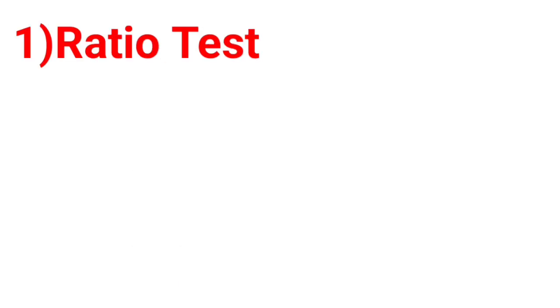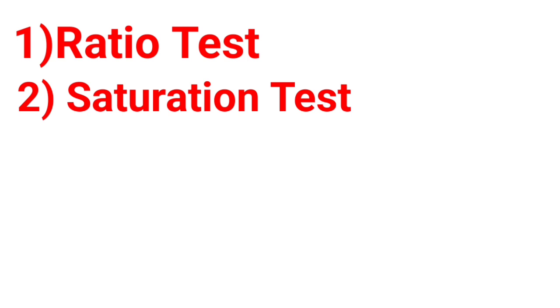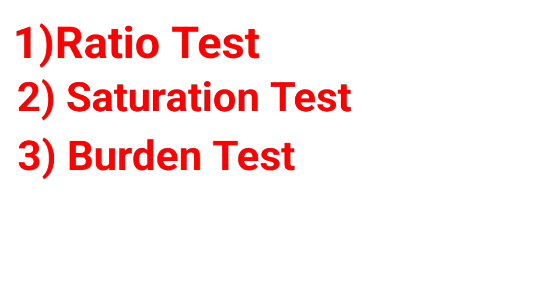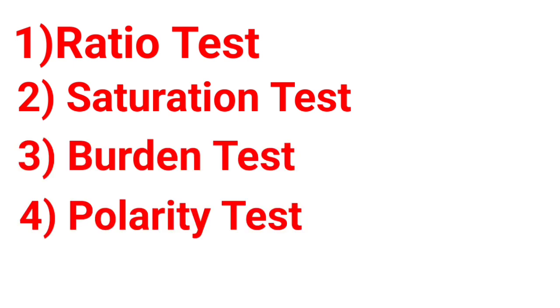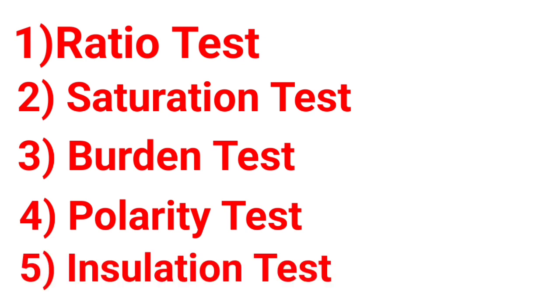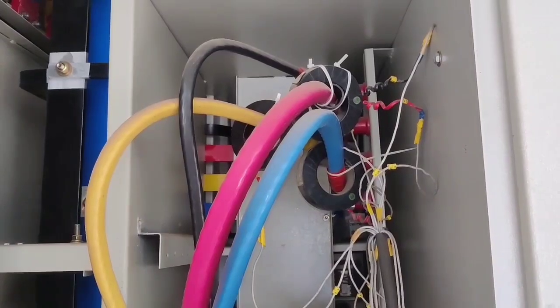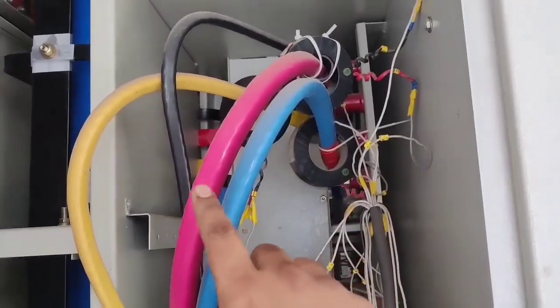The first method is the ratio test method — in this video we will identify whether a CT is OK or defective using this method. The second method is the saturation test method, and there is also the burden test method, polarity test method, and the last one is the insulation test method. We can identify CT condition by all five methods, but in this video we will identify it by the ratio test method.